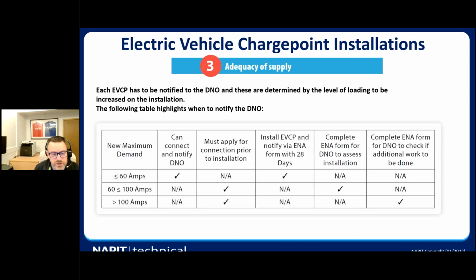So when we're looking at an EV charge point, it has to be notified to the DNO, and there are different levels of notification required by the DNO. The following table lists out what we're looking at. If it's less than 60 amps, it can be connected, but must then be notified to the DNO. So you've got 28 days to issue the ENA form, which is available from the ENA website, to notify the DNO that you have installed an EV charge point.